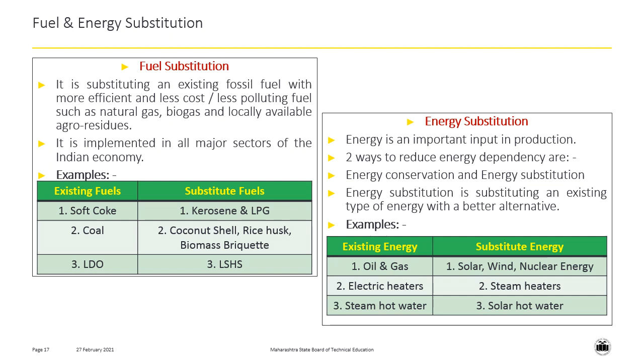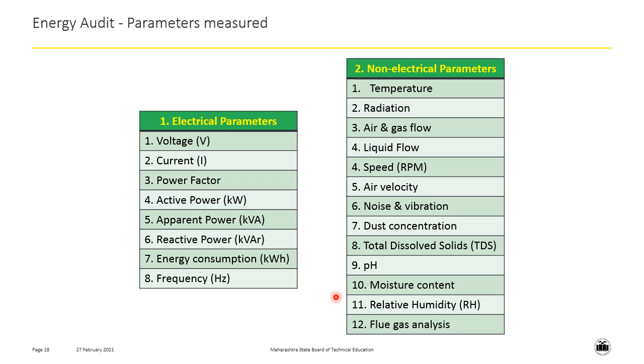So students, as we have learnt in the previous video, a detailed energy audit involves the measurement of various parameters in an industry. These parameters can be classified into electrical and non-electrical. In the electrical parameters, we can measure the voltage, current, power factor, active power, apparent power, reactive power, energy consumption, as well as the frequency. In the non-electrical parameters, we can measure the temperature, radiation, air, gas and liquid flow, speed, air velocity, noise and vibration, dust concentration, total dissolved solids, pH, moisture content, relative humidity, as well as we can analyze the flue gas. In the next slide, we will learn the different energy audit instruments which can be used to measure all these parameters.